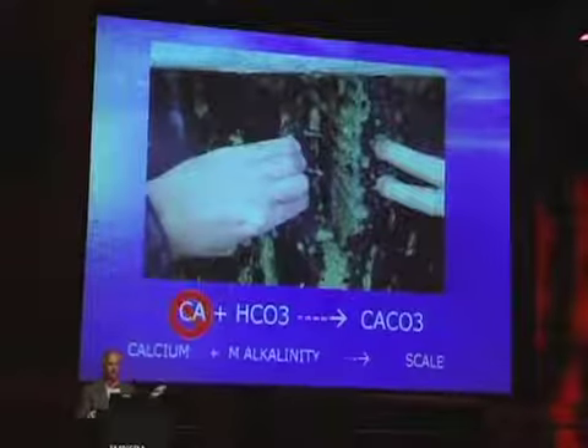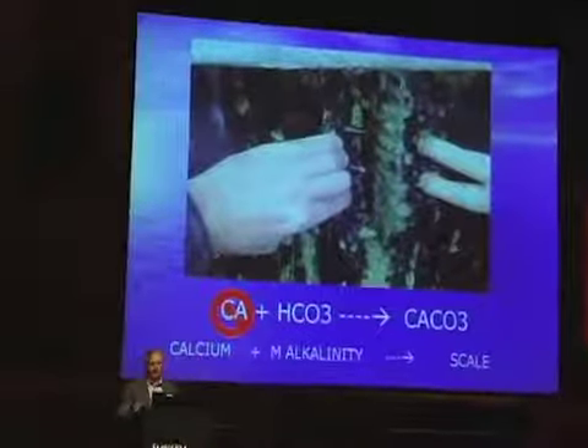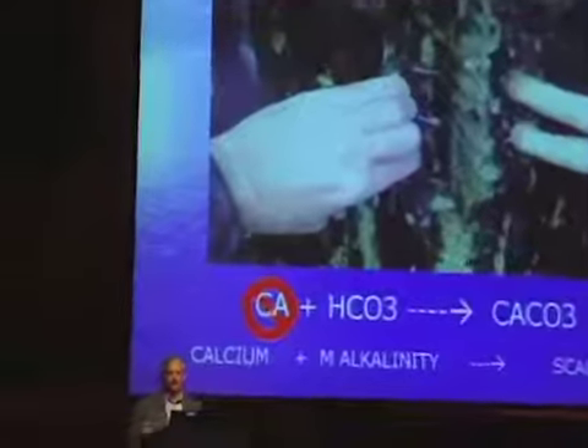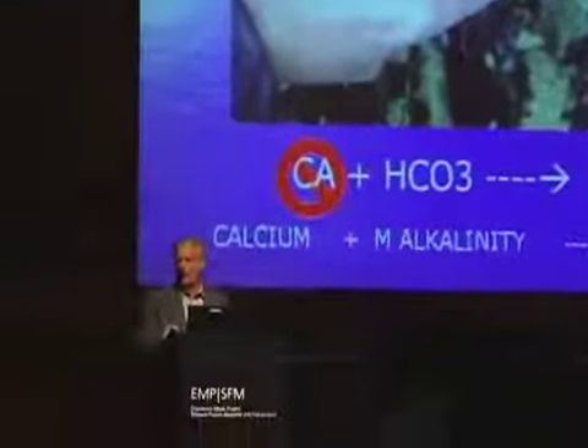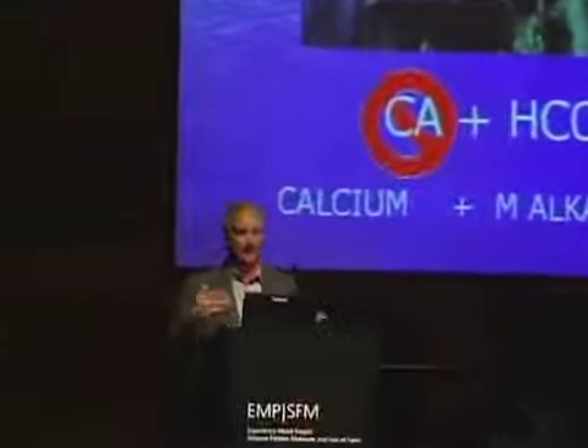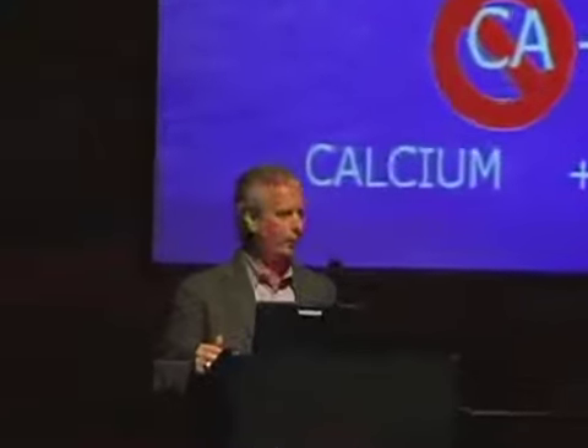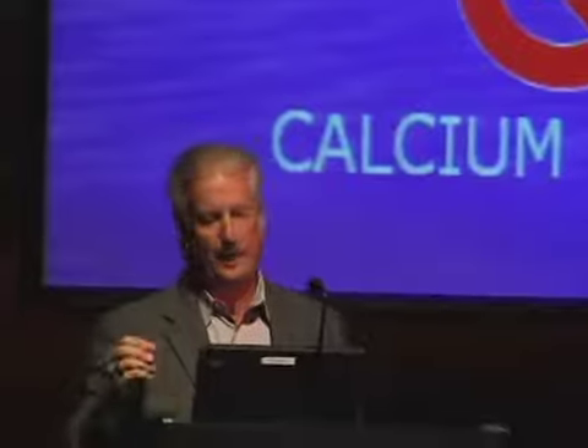Here's a situation in Indiana where a plant was using soft water, running the cycles up, and they lost the softeners for a month. No one was testing, no one did anything. They assumed everything was working until they saw their towers, and of course it all scaled up fairly quickly. So you need to be careful with some of this.